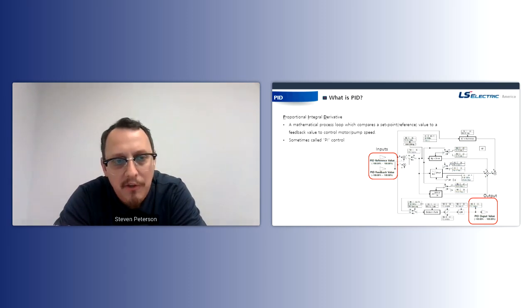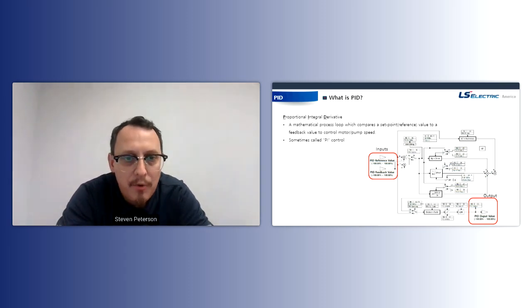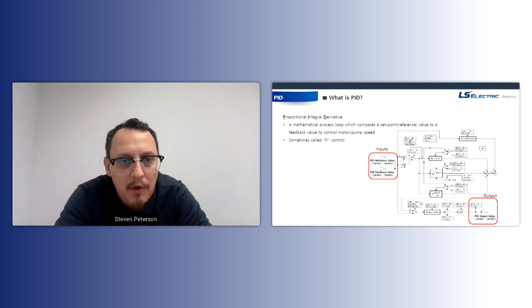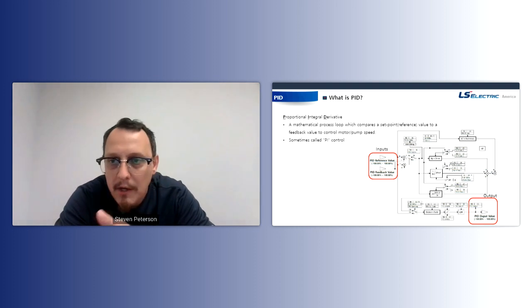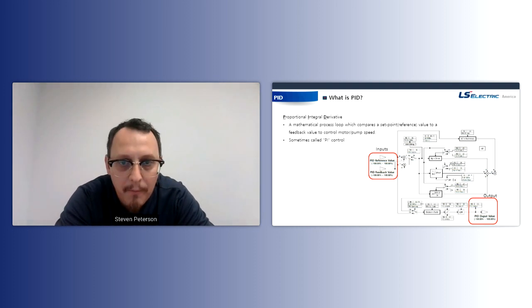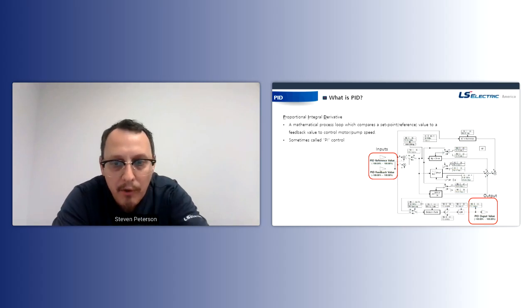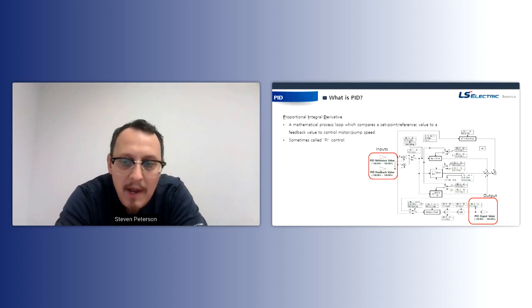So as I mentioned, it's a mathematical process loop, and what you're doing is comparing two inputs. One is your set point, or as we call it here, a PID reference, and the other one is your feedback. Your feedback could be a pressure transducer, for example. And what we're going to do is compare the two and calculate an error between them. So if you have a 60 PSI set point, but your feedback is at 55 PSI, we're going to output a PID value after we go through this algorithm, and we're going to adjust your motor speed to compensate for that difference.